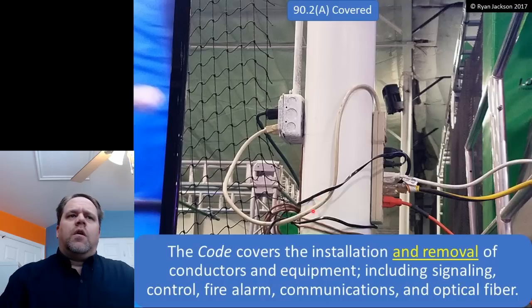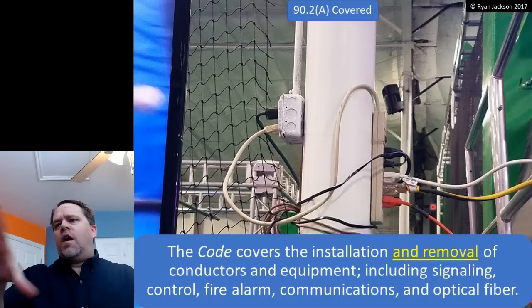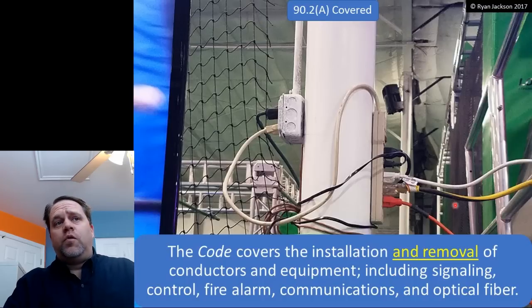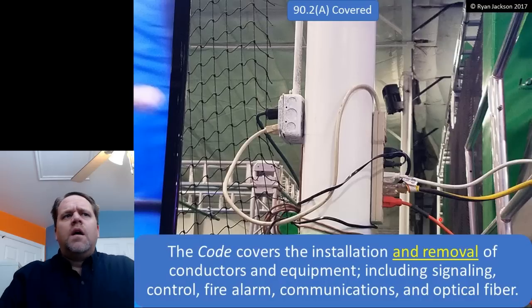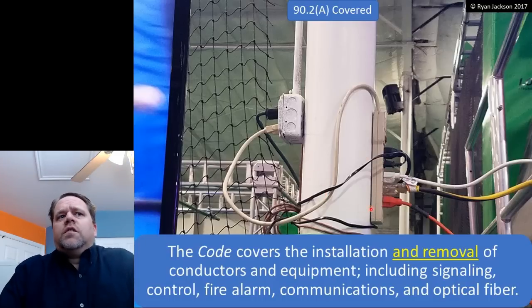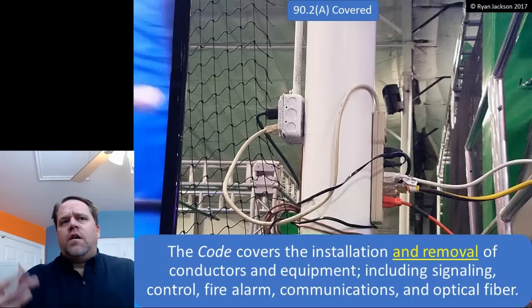One of these was going to a radio, and another one was going to an oscillating fan, to keep everybody cool while they're working out, and another one was going to a portable light or something. None of this was really part of any electrical installation. So is this a code violation? No, not really, because this is not an electrical installation. It's the usage of electricity.